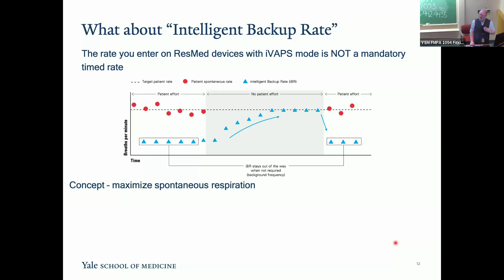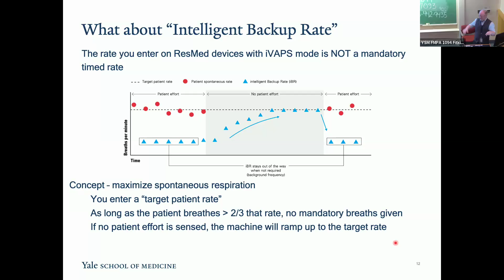In the background, there's a background frequency, which is 2/3 of the target rate you entered. As long as the patient is breathing above 2/3 of your target rate, there will be no mandatory breath given. So if you enter 18, if the patient's breathing at 17, nothing happens. 16, 15, 14, 13, nothing will happen. If the patient hits 12, that's 2/3 of 18. That's the point at which the backup rate is going to kick in. So the actual mandatory rate when you set 18 is 12. And if no effort is sensed, the machine will start at 12, and then it'll ramp up the breath rate to that target rate of 18 until a spontaneous breath is detected. And then it drops to that background sensing of a breath rate of 12.